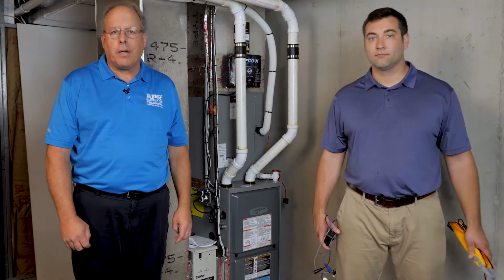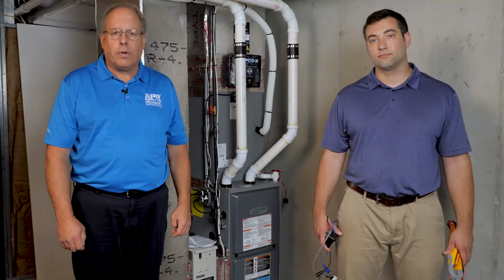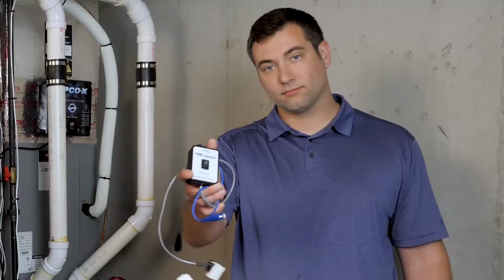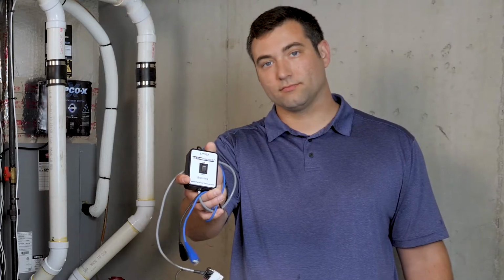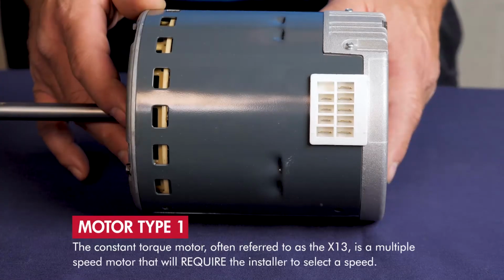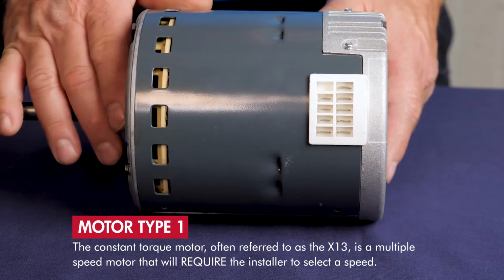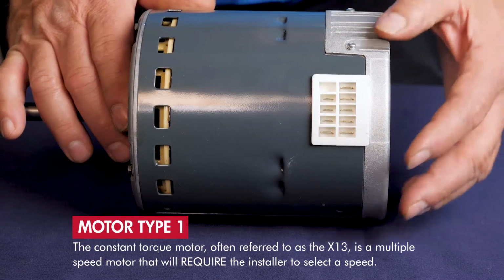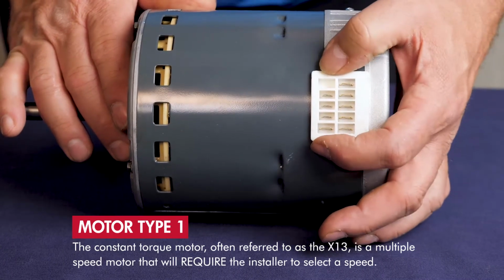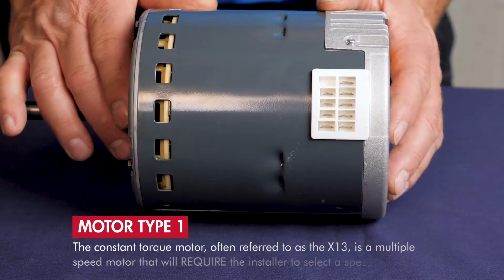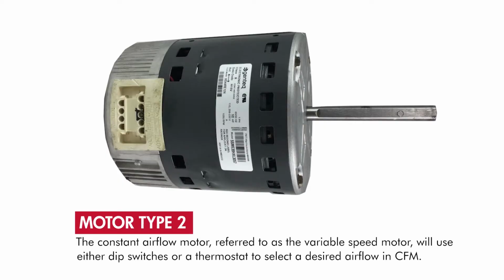To troubleshoot the variable speed or constant airflow motors really requires that you use the manufacturer's recommended troubleshooting tool for that motor. The constant torque motor, often referred to as the X13, is a multiple speed motor that will require the installer to select a speed or torque rating to adjust airflow. The constant airflow motor, referred to as a variable speed motor, will use either dip switches or a communicating thermostat to select not a speed but a desired airflow in CFM.